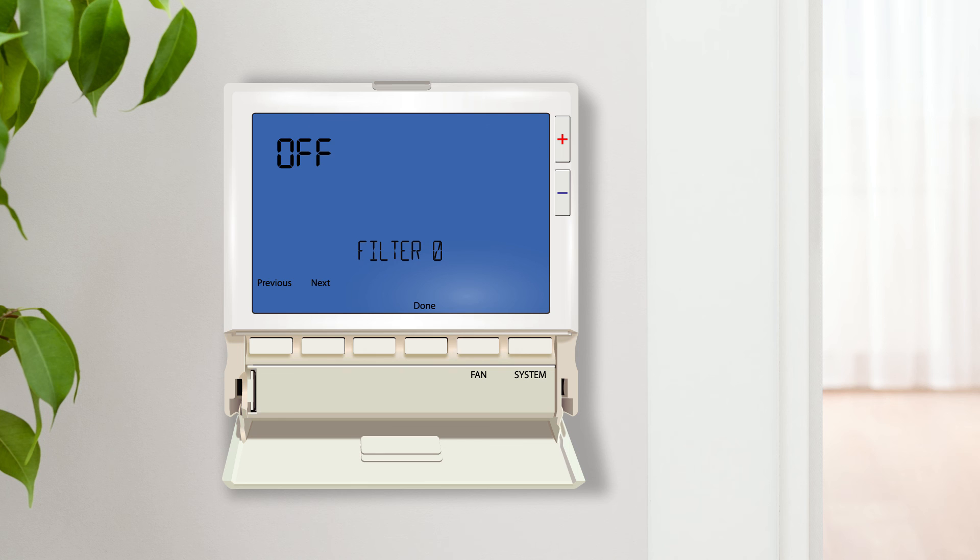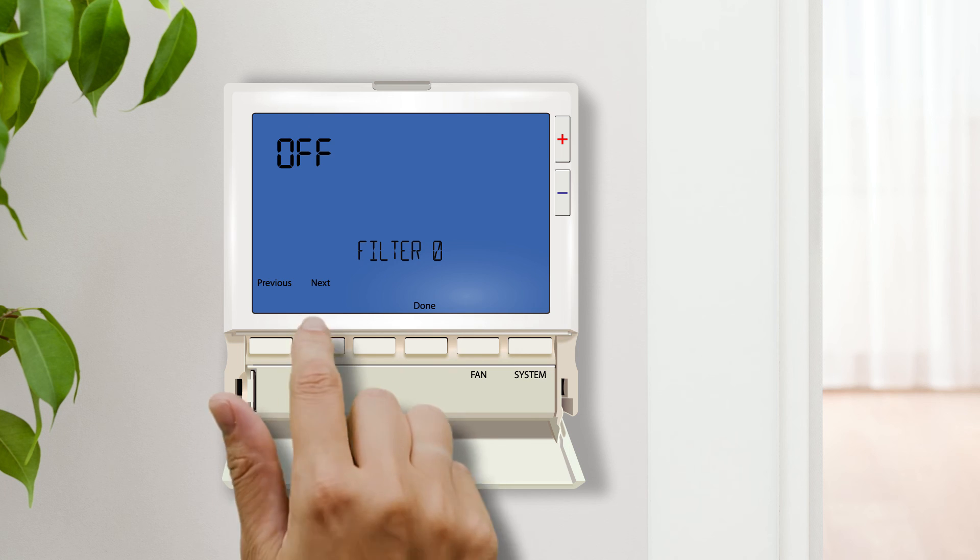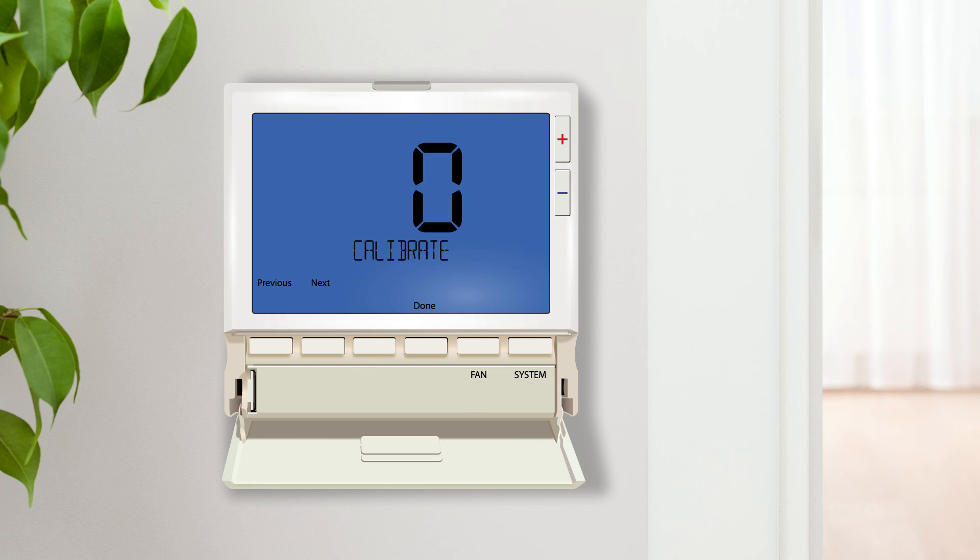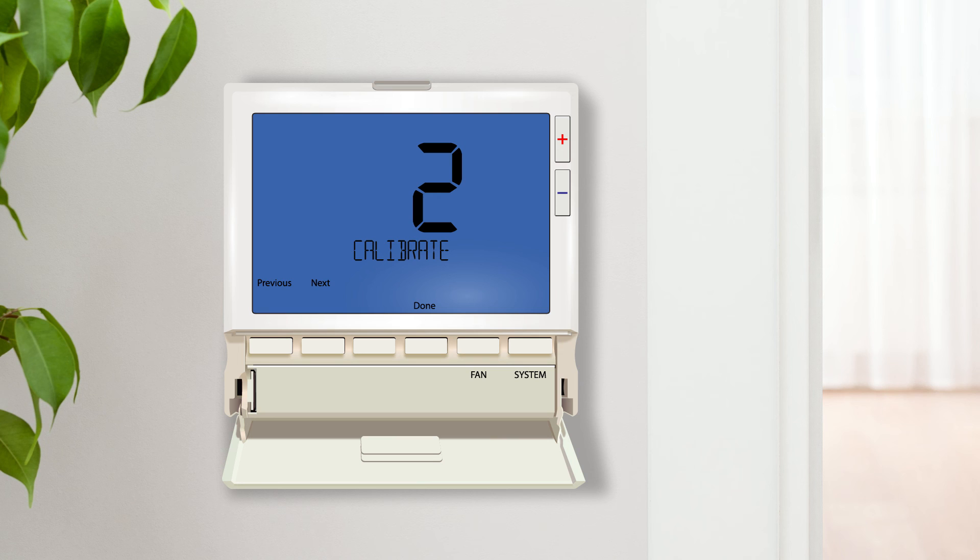This setting defaults to off. Room temperature calibration allows you to offset the displayed ambient temperature up or down as many as four degrees. For example, if you choose two degrees, the thermostat display will read 70 when the actual temperature is 68. This setting defaults to zero.